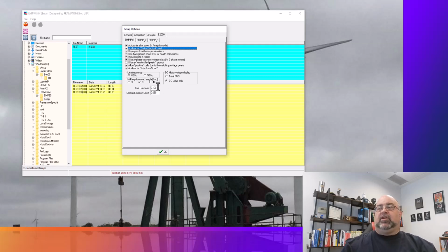You can update to your kilowatt hour cost, and your carbon emission should be for doing correction, so it's the reduction value. Right now 0.699 metric tons of CO2 per megawatt hour, which is how the software is going to calculate it, is the national average. Now, if I was inventorying per ISO 50001, then I would be using a different number. That's actually based upon the base loading. So put that in there, leave this all the way it is. These are all defaults there.